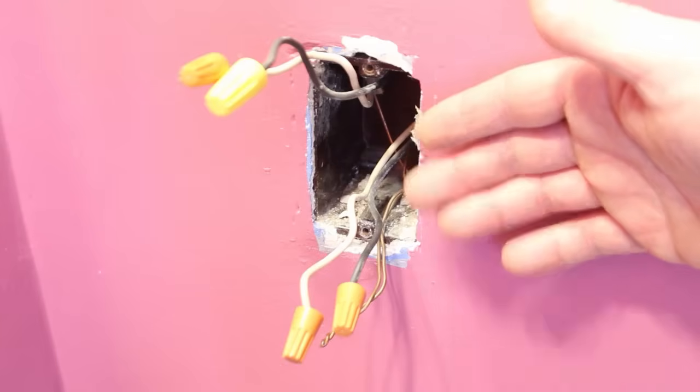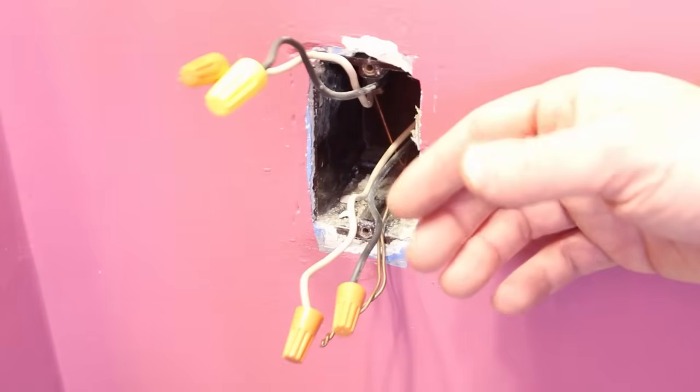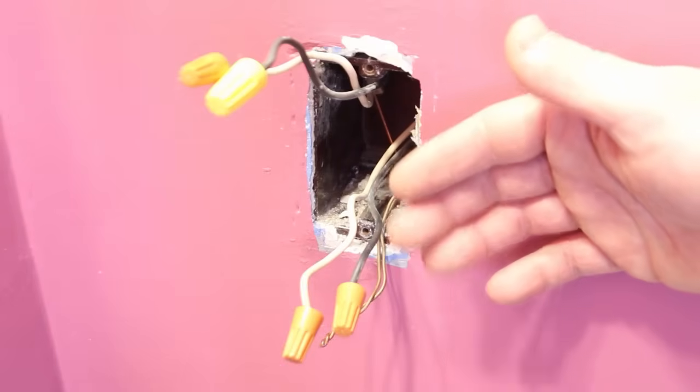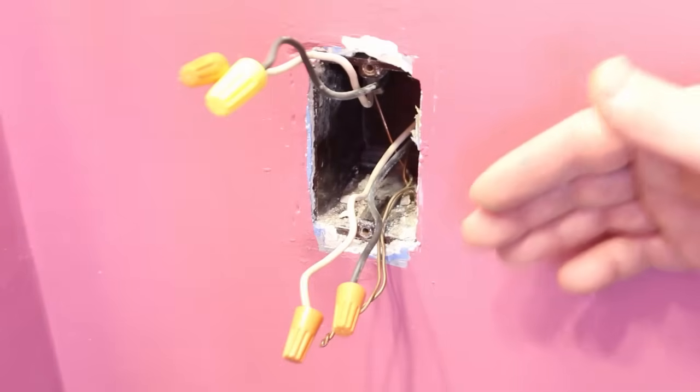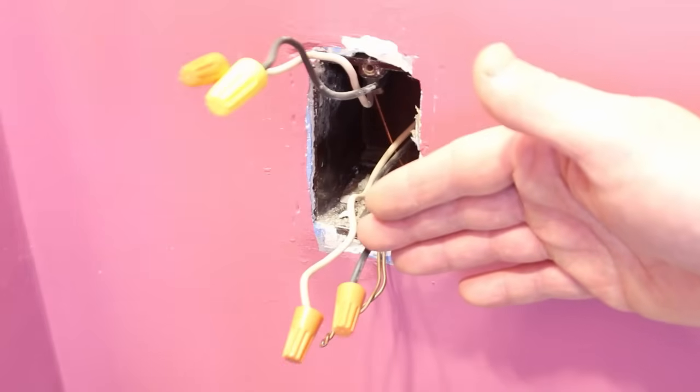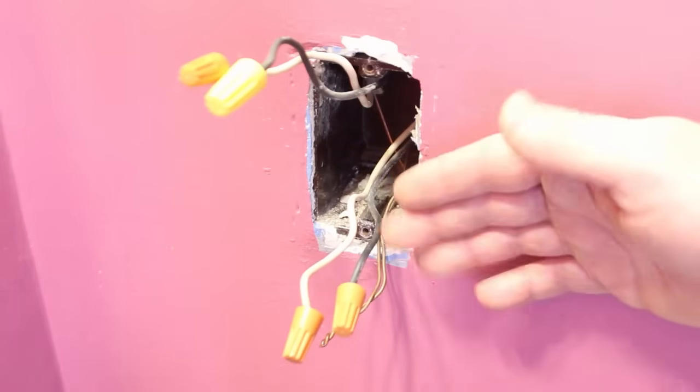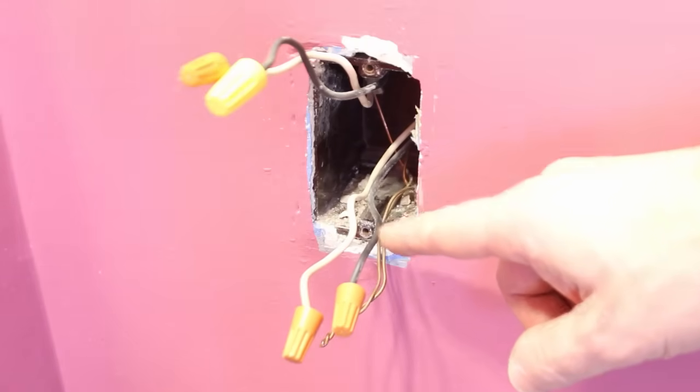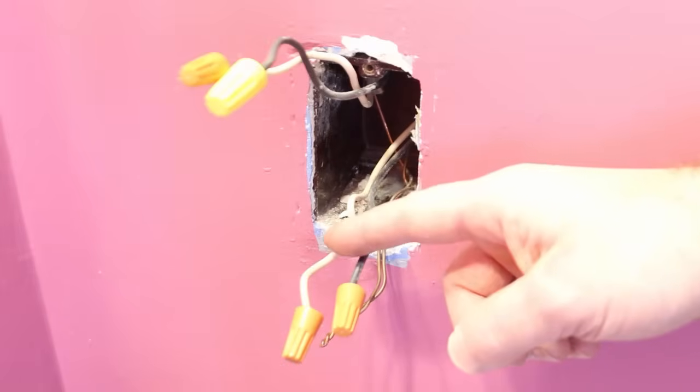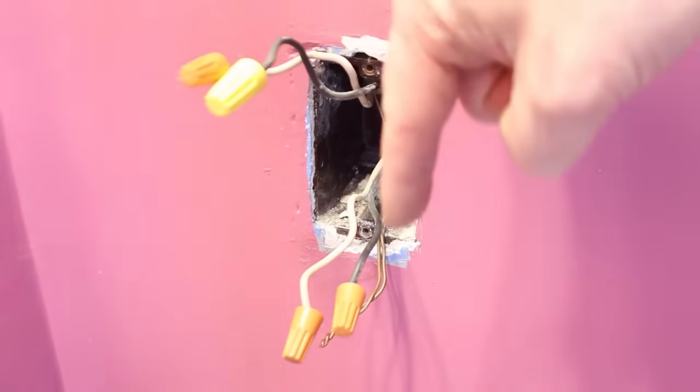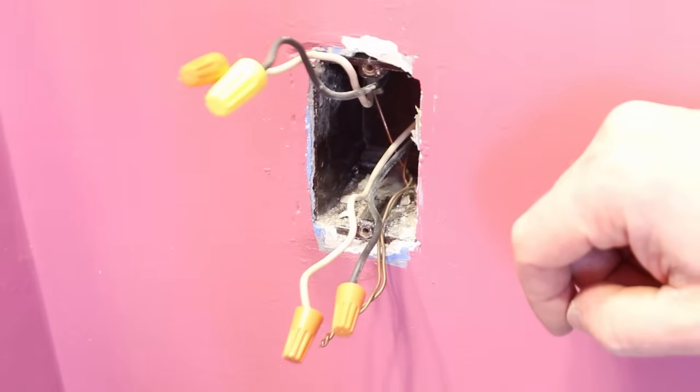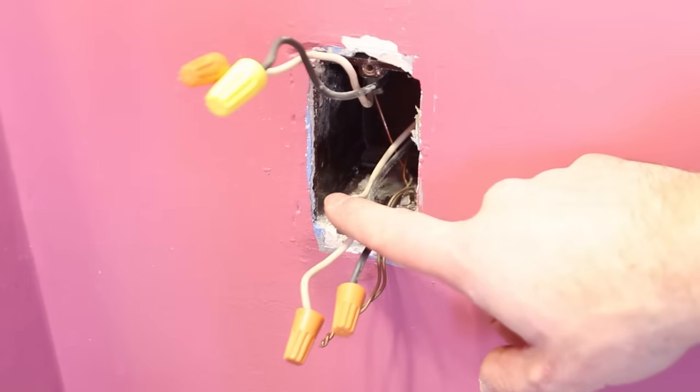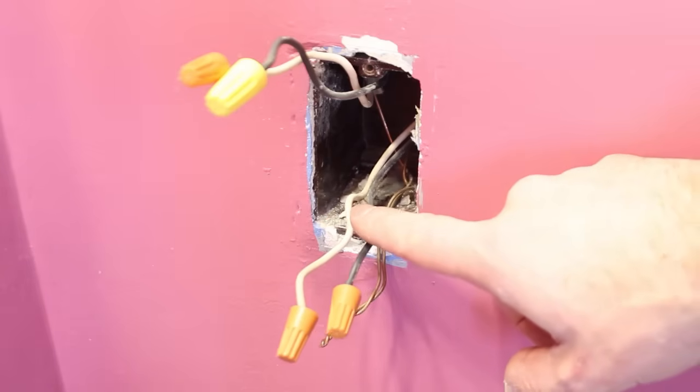The line wires carry electricity from the source—for example, another outlet or the panel—to this outlet. So we need to figure out which wires are the line wires and which are the load wires. My guess is that these are the line wires, the wires carrying electricity to the box. Why is that my guess? Well, my electric panel is below us in the garage, and these wires are coming up. So chances are this could be the electrical source.